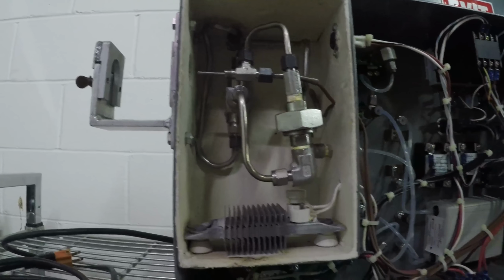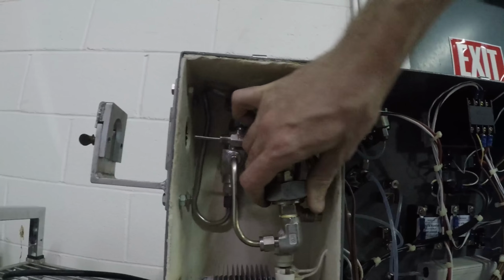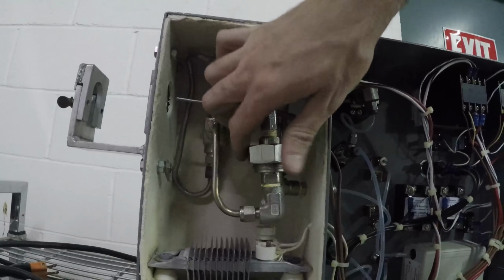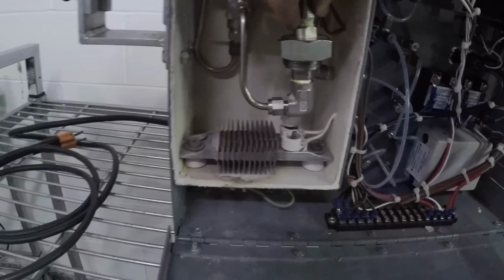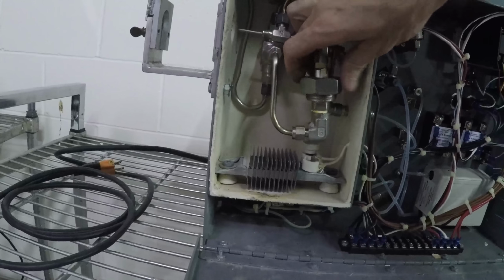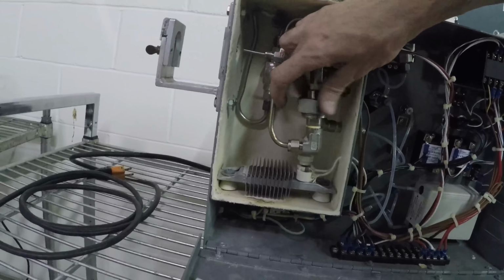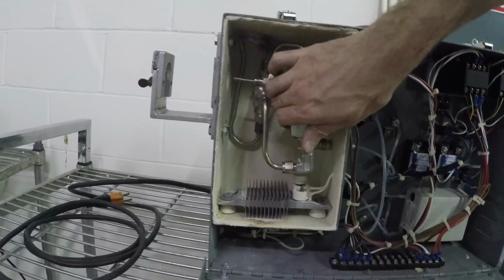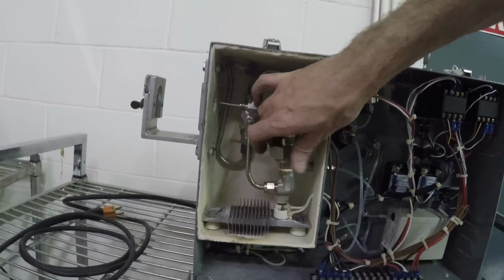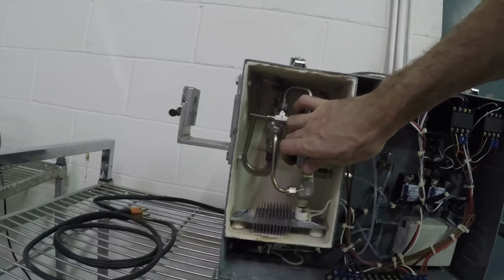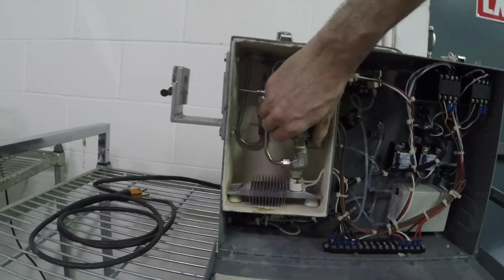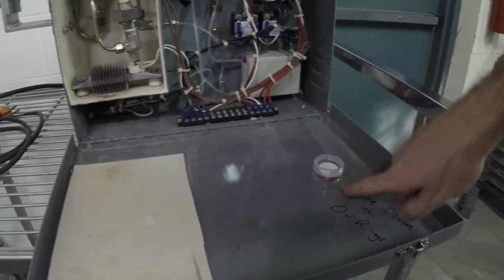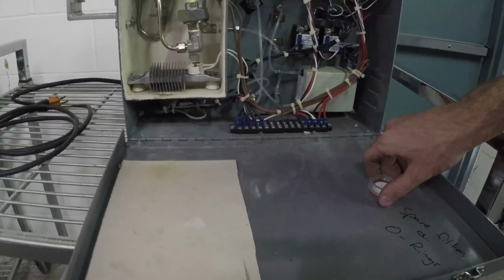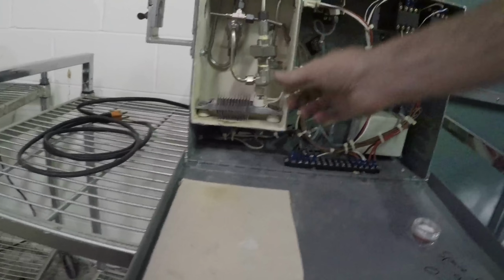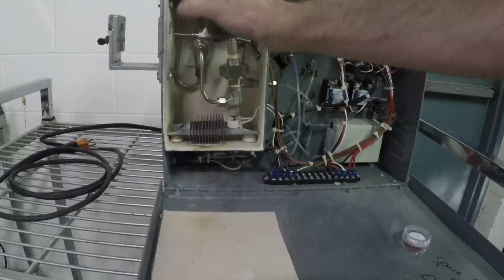Inside this filter box, which should only be finger tight, is an O-ring and 2 metal screens with a filter in between them. When it comes to you, it is ready to sample. You should not need to change this filter. However, if you are doing a lot of sampling or multiple runs, or you happen to be doing several that are very dirty, we ship spare filters, and if you run into a problem, O-rings with each sample unit. To reassemble, it should just be finger tight.